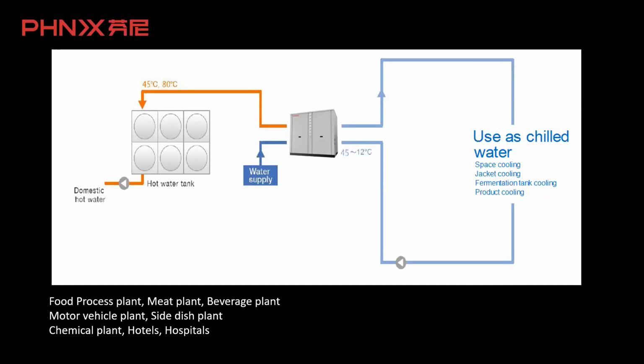And for the evaporator side, the maximum inlet water temperature can be 45 degrees. Which means it can be used not only for traditional air conditioning, but also in industrial applications where the water temperature is higher. Then we can use it for the heat recovery function for the HeatMax. Yeah. Okay. Let's move on.